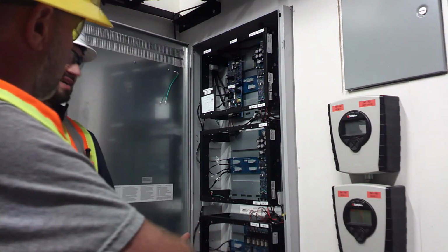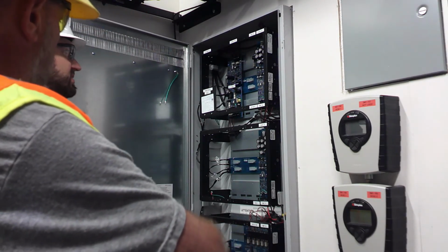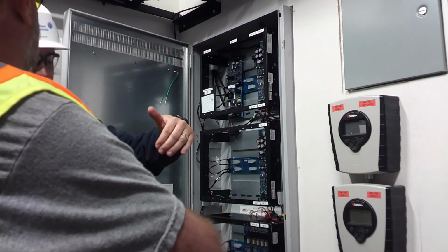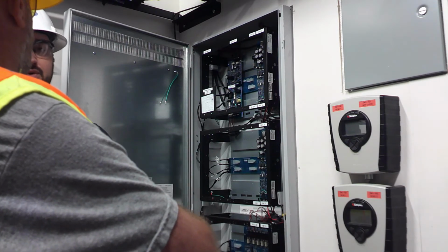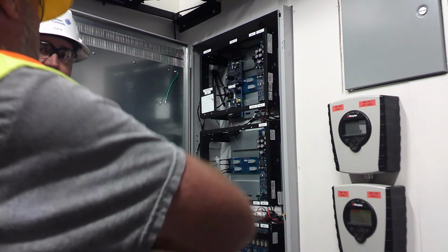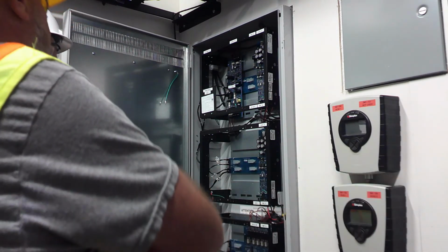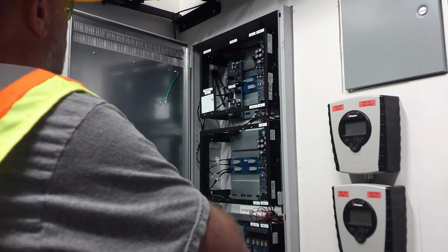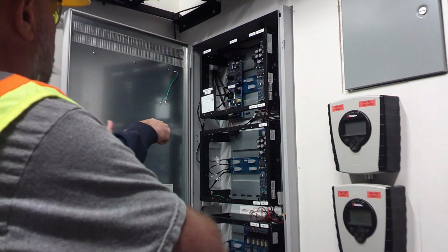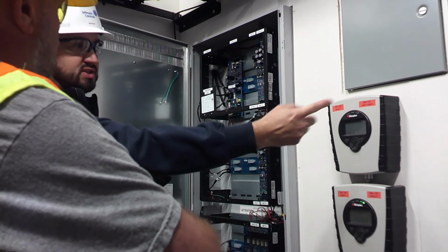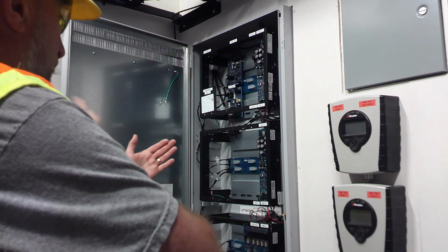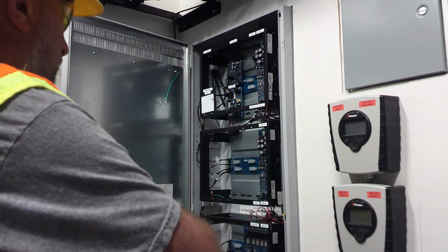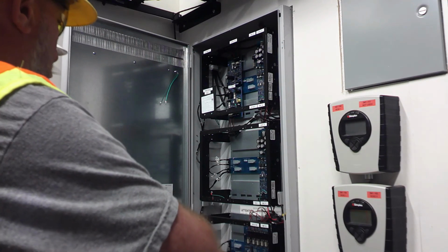The chances of that happening are slim, that's why they have a Class A loop, because it goes out 2 ways. You would literally have to have a break come out of both of those to have something like that happen. So it doesn't go one way, it goes another way. Yes, that's why I was saying, if there's a break between here and the main panel, instead of just the short jumper, it would still get there. It would just have to go through all 4 other panels to get back to the main panel, which is a matter of seconds, or milliseconds, to get that data transfer.